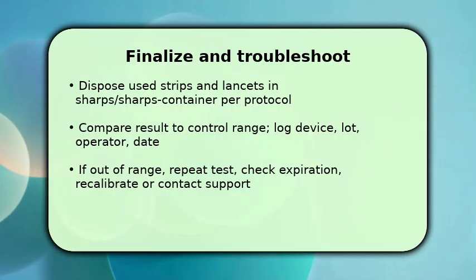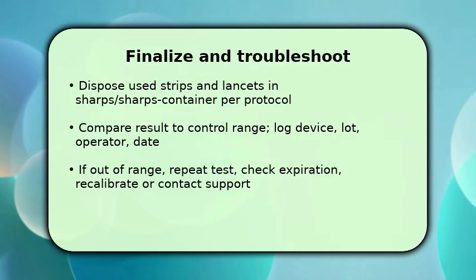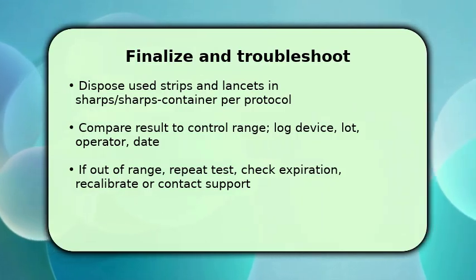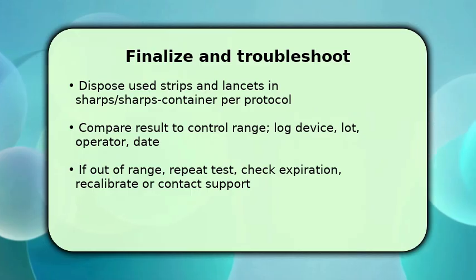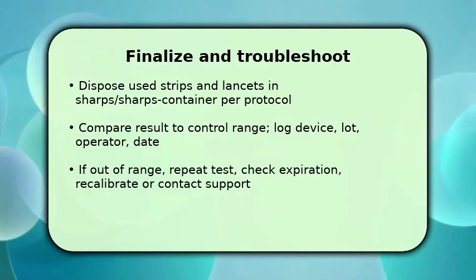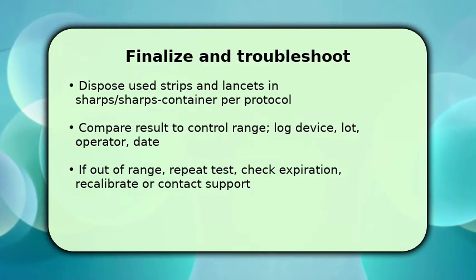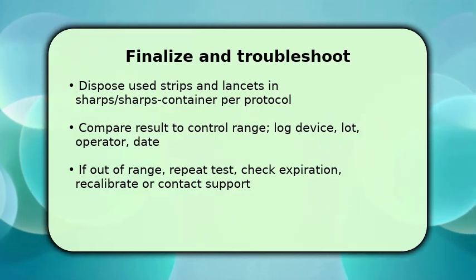If the result falls outside range, first repeat the test with a new strip and fresh control solution to rule out technique. If still out of range, verify strip expiration and meter calibration. Then escalate to your supervisor or technical support for further troubleshooting.